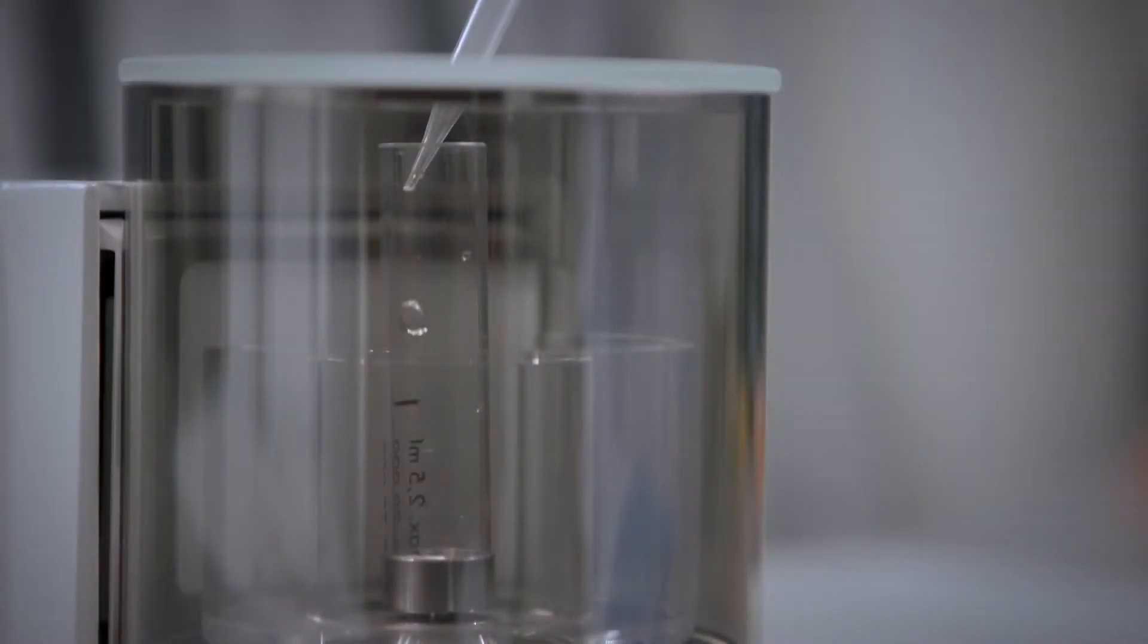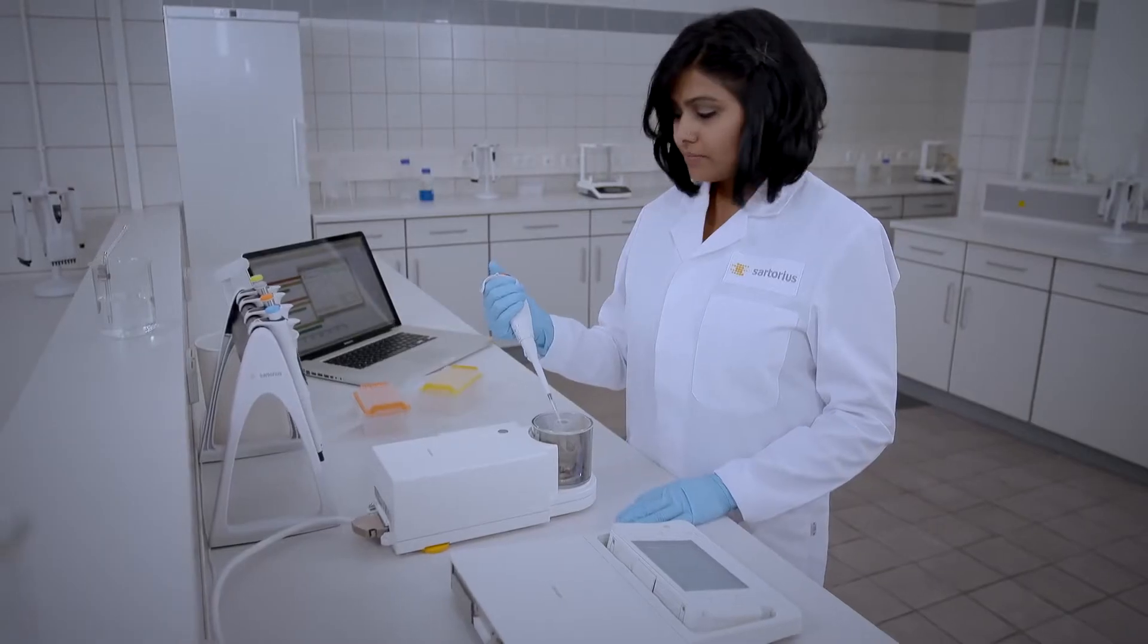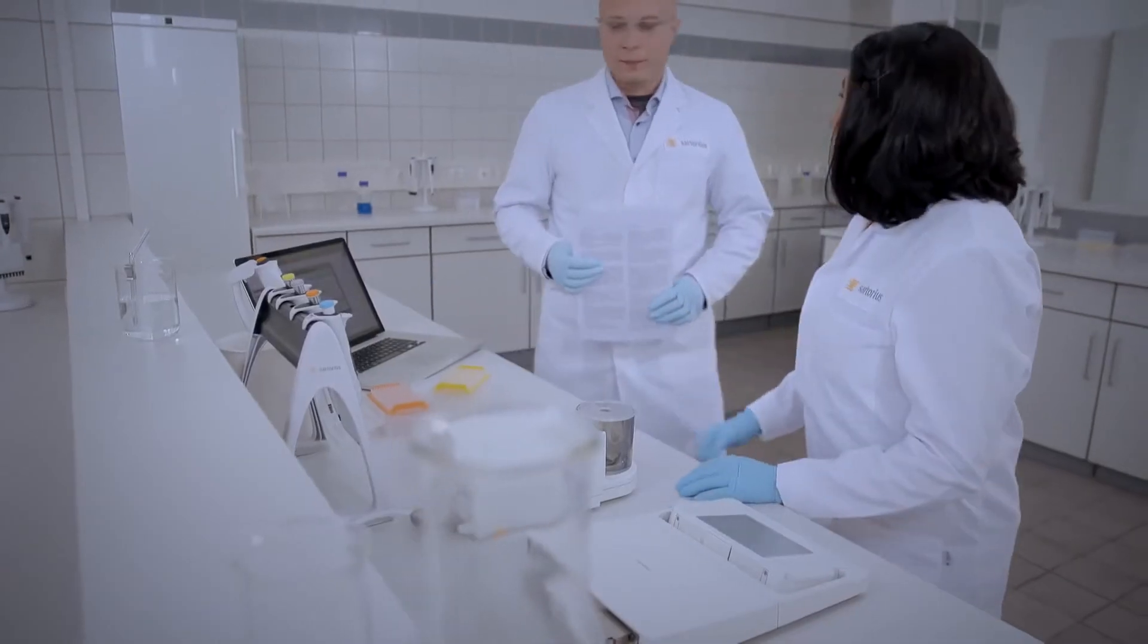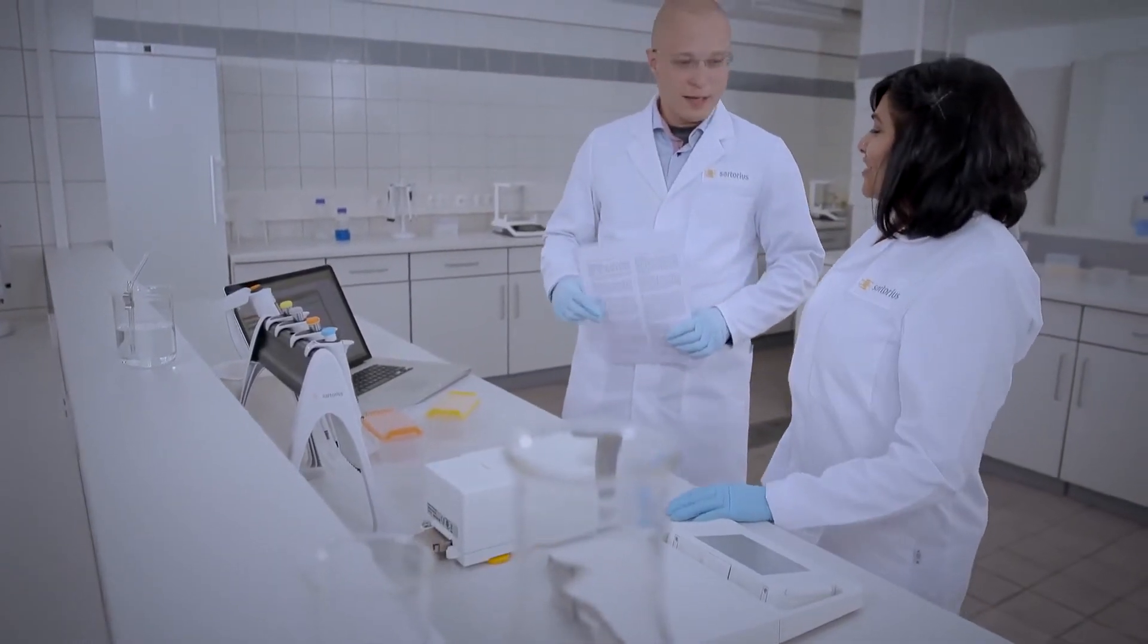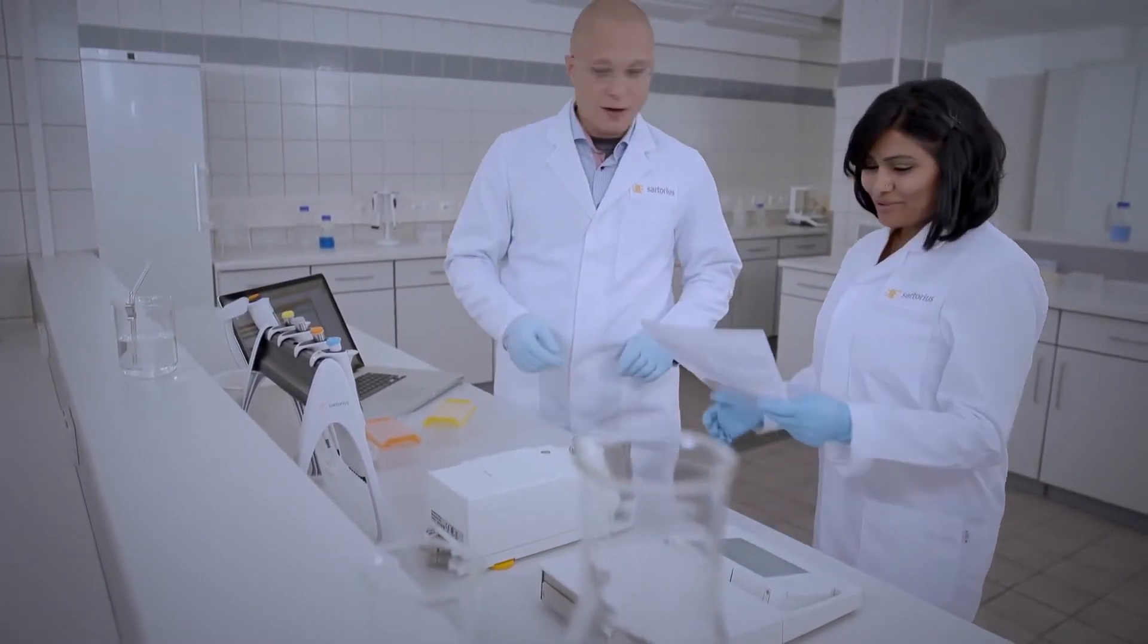A calibration certificate is as important as the calibration procedure itself. It documents your results, as well as the equipment and people involved in the process. An accredited certificate will also show the uncertainty of measurement for your instrument.